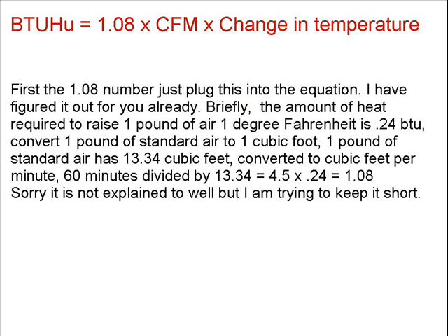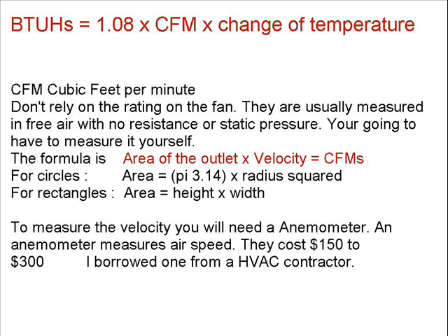First, the 1.08 number. Just plug it into the equation. I've already figured it out for you, and you can read the explanation if you need. Cubic feet a minute. You can't rely on the rating of the fan because they're usually measured in free air with no resistance or static pressure. You're going to have to measure it yourself.